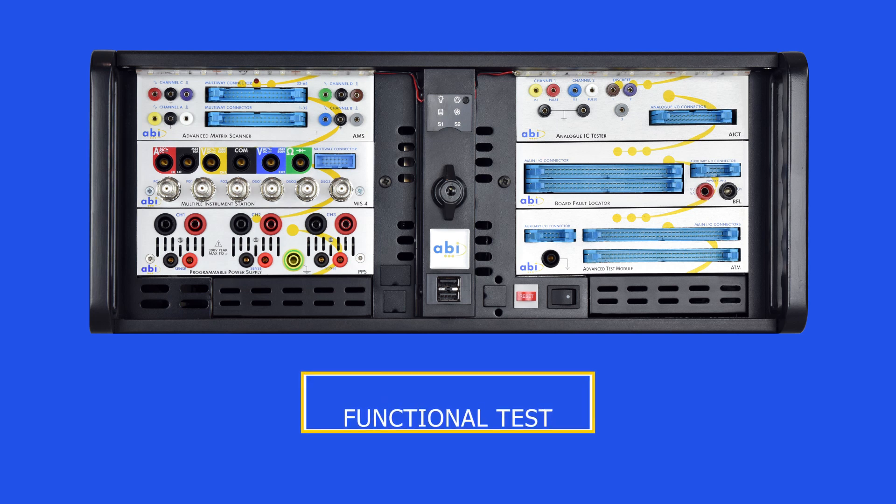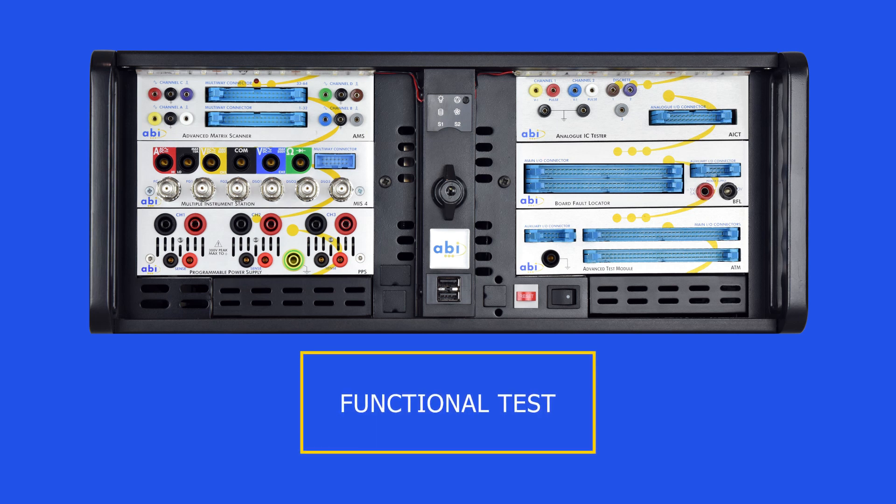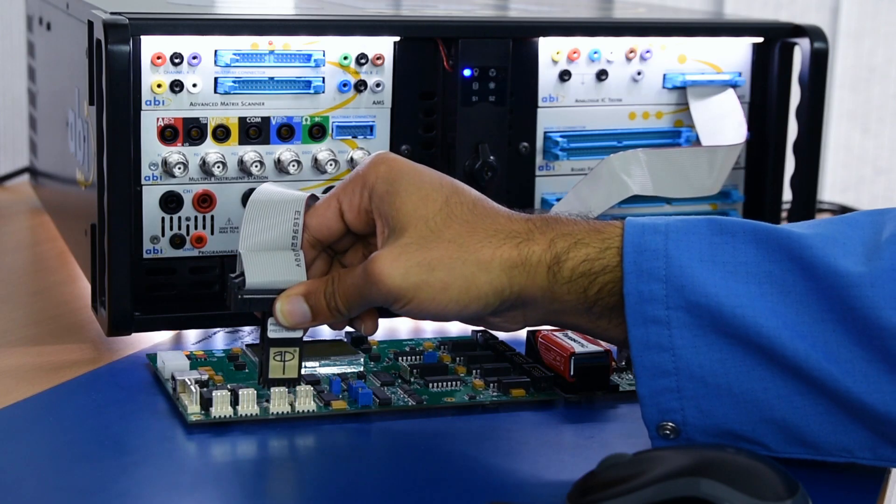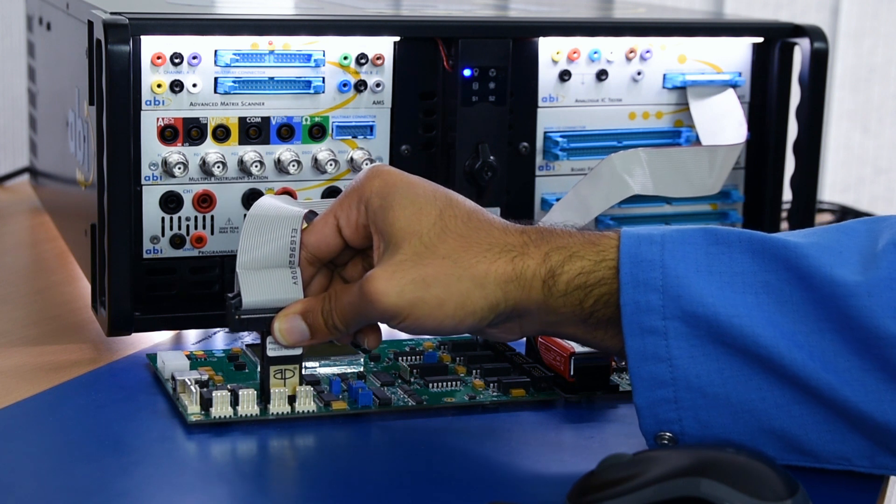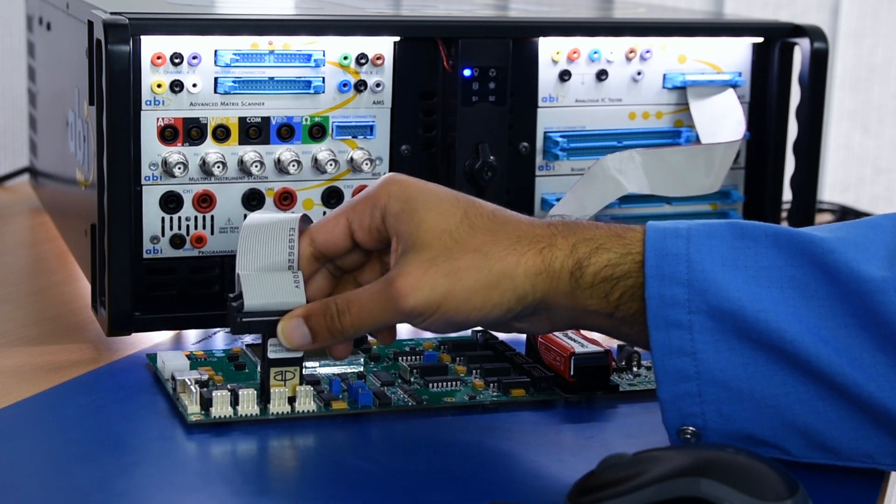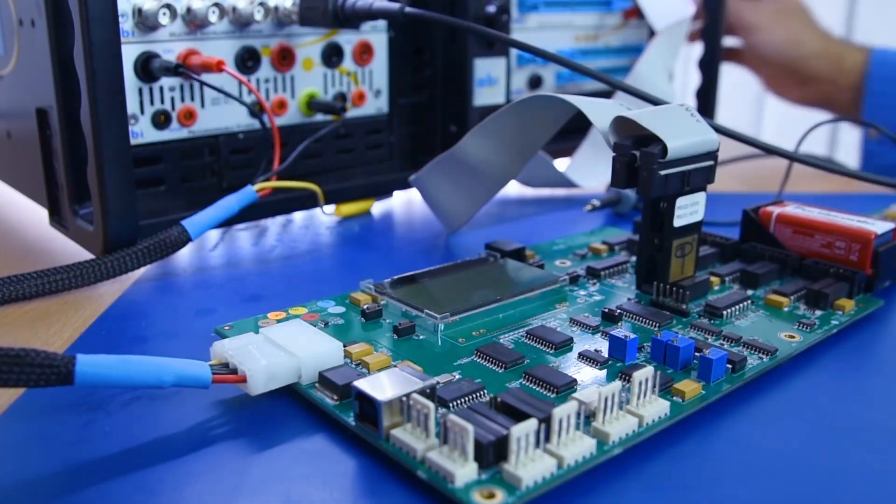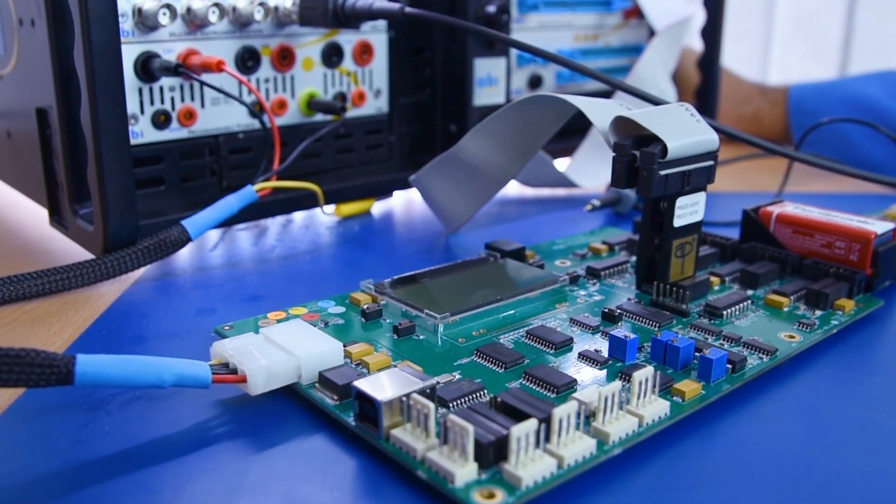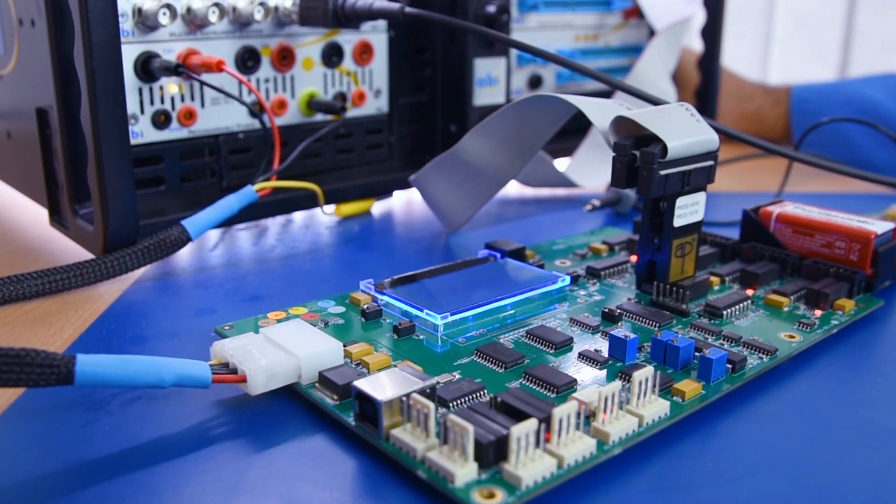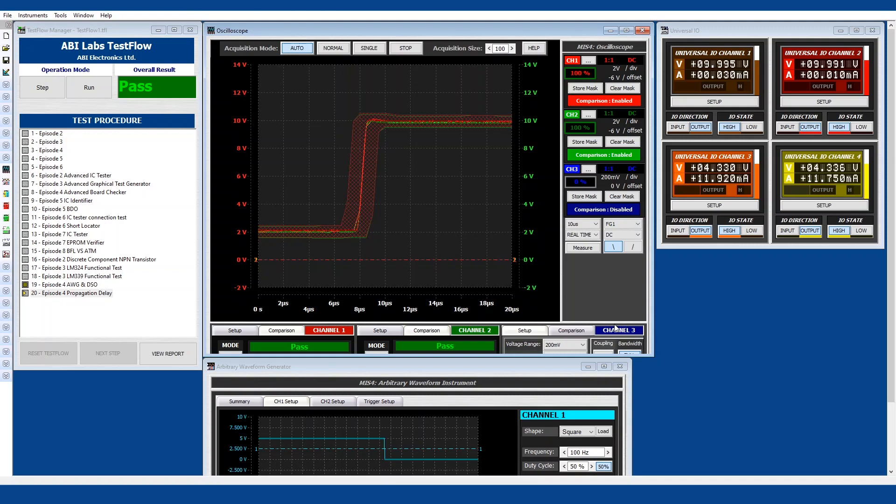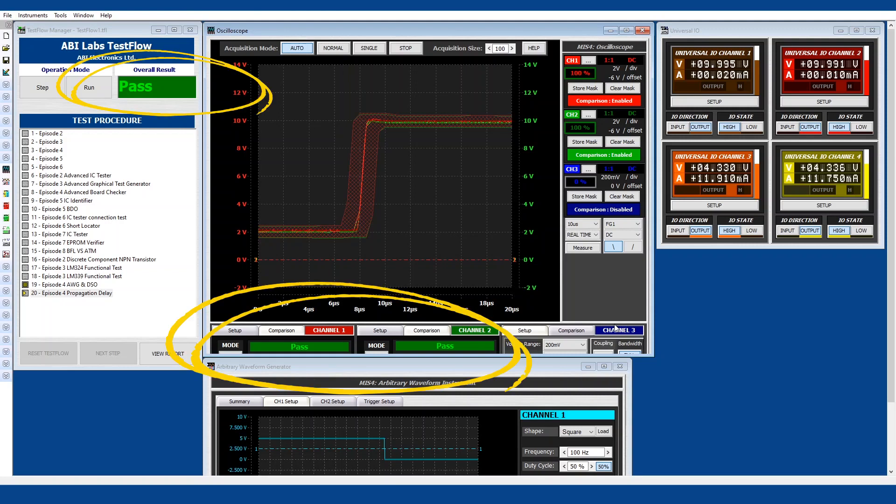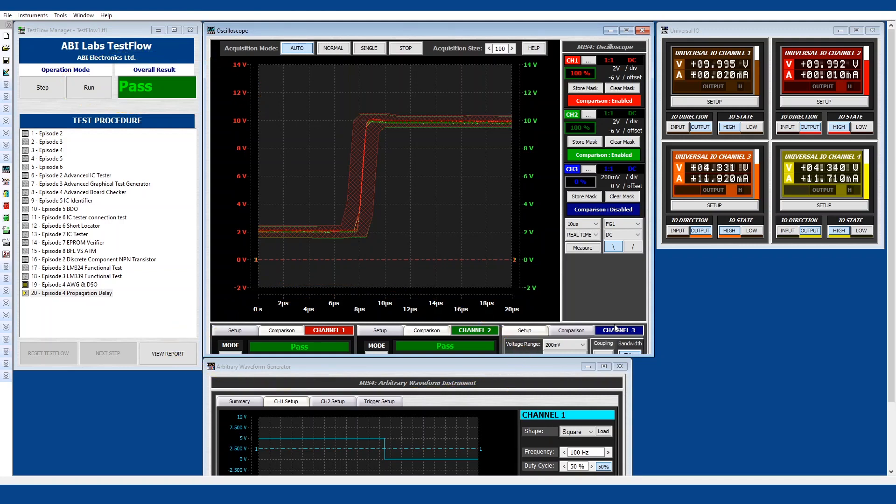Once they implemented the Boardmaster into the repair and maintenance department, they were carrying out a functional test using the AICT module and this test was telling them whether the device was passing or failing. However, this test did not give them more detailed information like a parametric test would do.